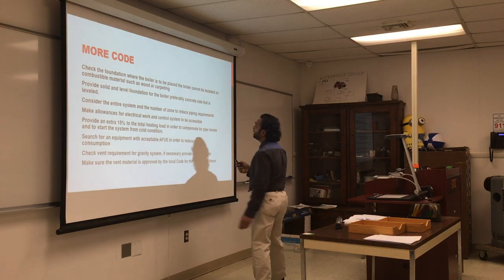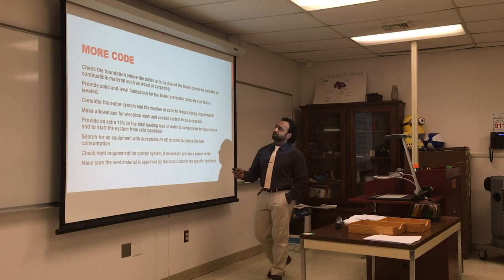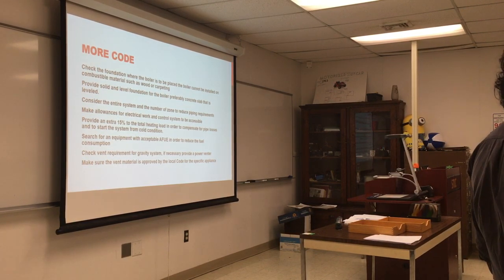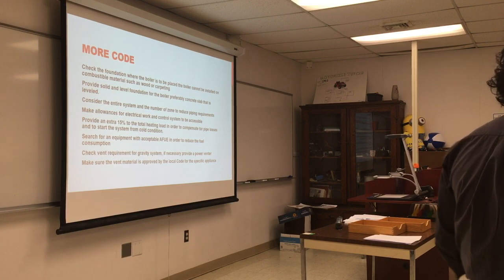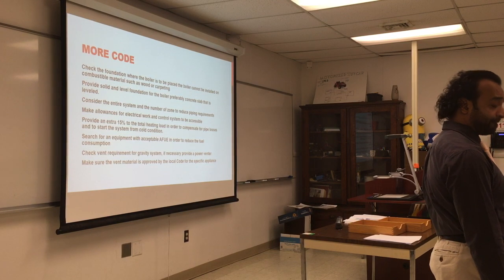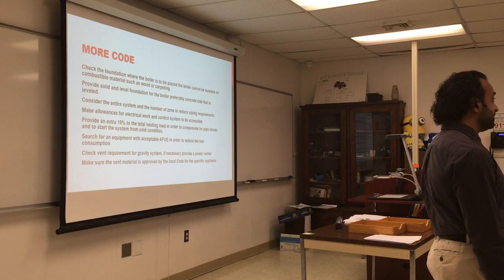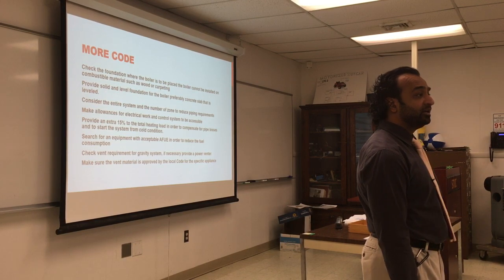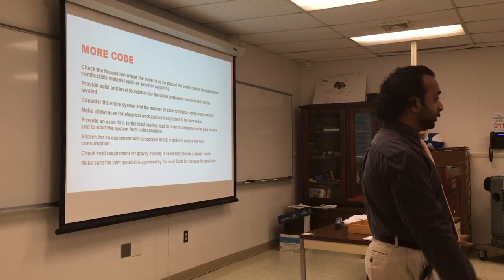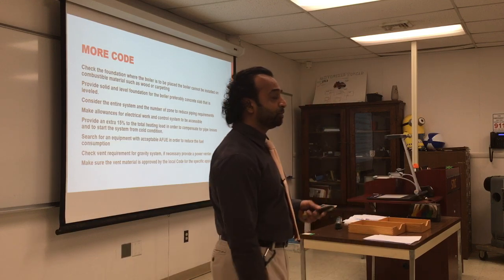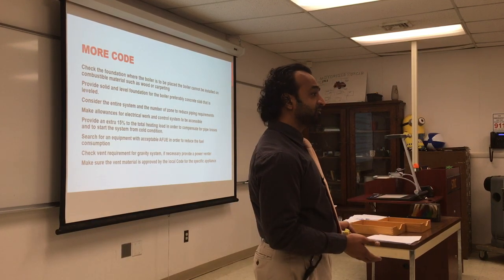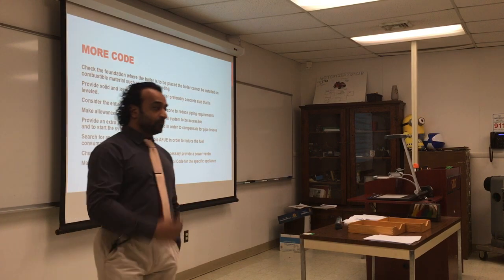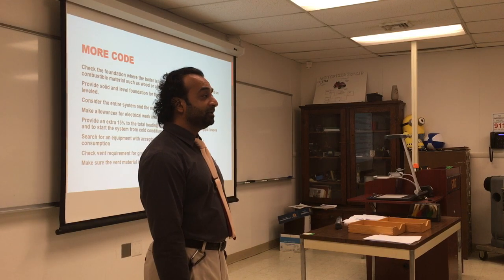Check the foundation where the boiler is to be placed. The boiler cannot be installed on combustible materials such as wood. If you have hardwood floor in the basement, you cannot put the boiler on it — it has to be on concrete. The concrete should be a little elevated; being at floor level is not ideal, especially for maintenance. For good practice, you want a pedestal about 10–12 inches high, the size of the boiler. I've seen boilers installed on attics — it's not code.